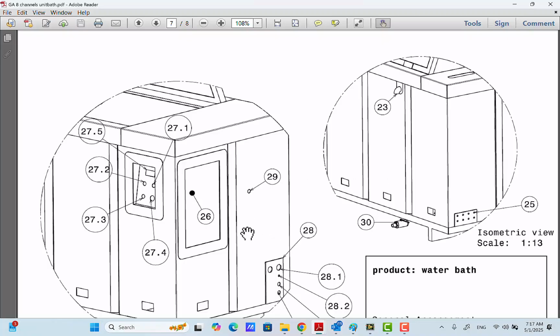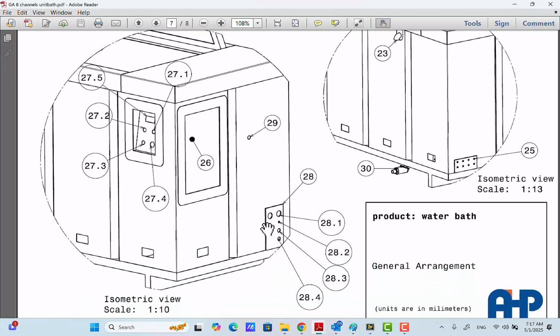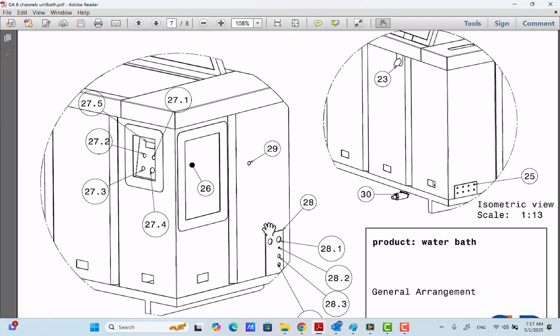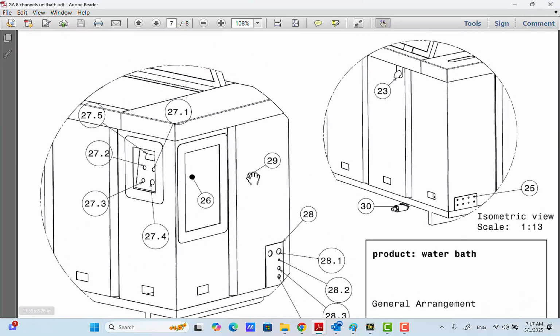Of course, in this test tank, you also need deionized clean water because you have a heat exchanger inside, you have a heating element inside this tank, a resistance heating element. For the long life and proper working of the machine, you need clean deionized water to keep the heating element safe for long life.